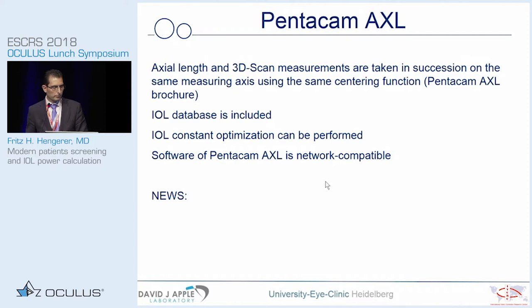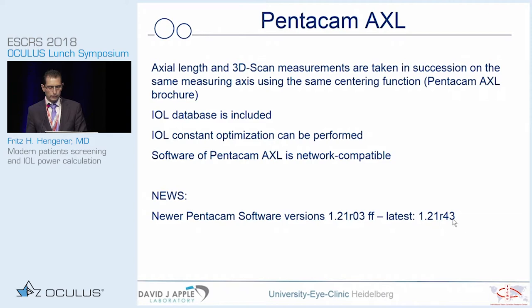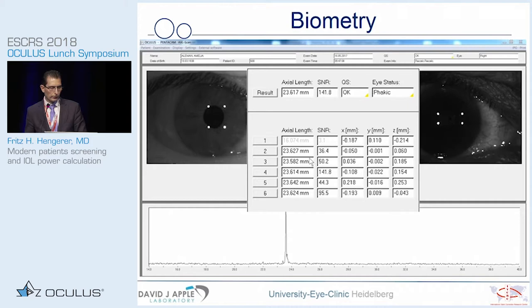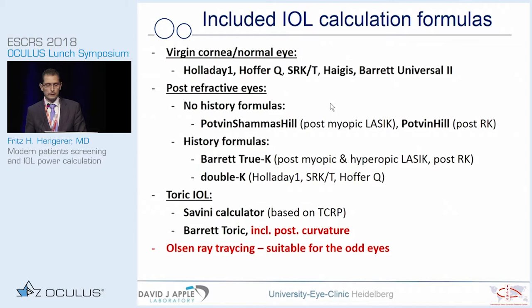You can perform constant optimization for up to 25 surgeons at your site with the current software. It is network compatible and the latest software version is 1.21R43, available on a free-of-charge basis. It is faster and allows measurement of more dense cataracts. An intelligent mathematical algorithm allows the machine to select the right values for axial length — it performs six single measurements and the most reliable one is chosen.